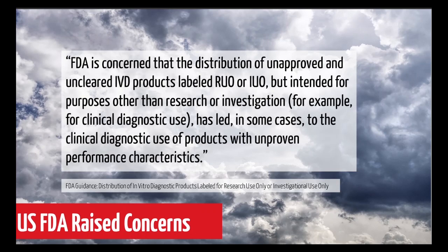So the FDA raised a few concerns a few years ago. It was stated here that FDA is concerned that the distribution of unapproved and uncleared IVD products labeled for research use only or for investigational use only, we will define that later, but intended for purposes other than research or investigation, for example, clinical diagnostic use, has led in some cases to clinical diagnostic use of products with unproven performance characteristics. If I'm informed correctly, this was also the case in the Theranos scandal.